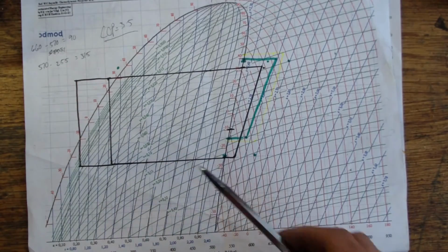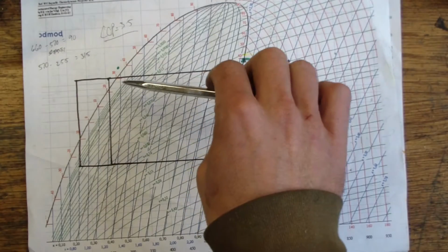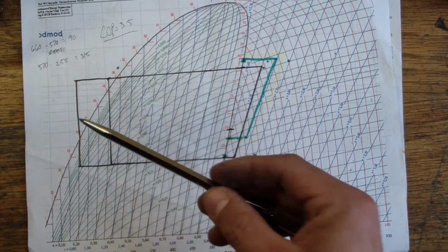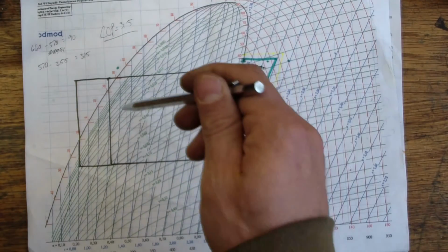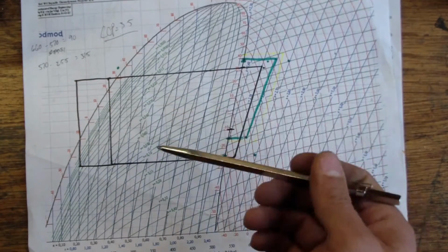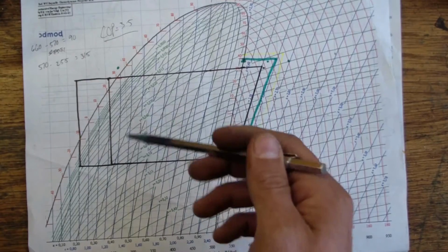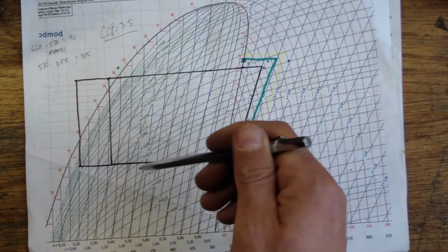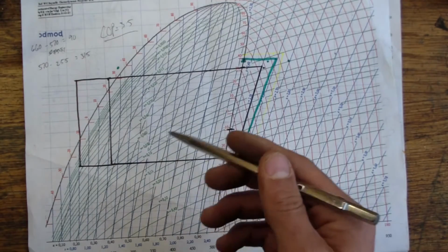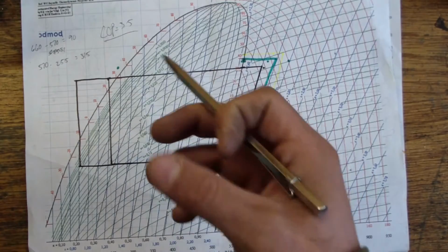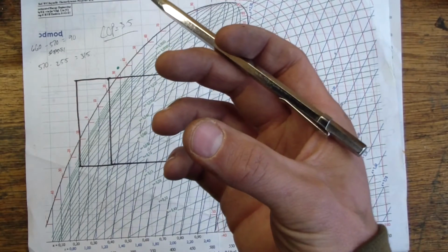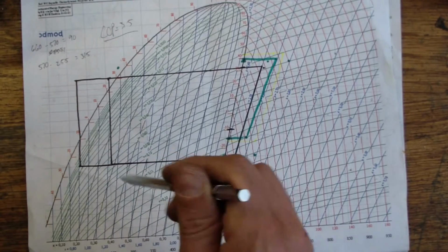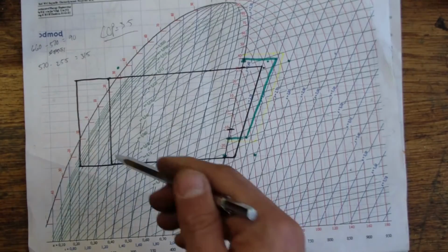we enter an area of the evaporator that's at a much lower pressure. And most of that pressure component that turns into velocity ends up finally resulting in flash gas, because all that high-speed liquid refrigerant coming out of the throttling device immediately starts to get very turbulent and all mixed up, and it essentially amounts to kinetic energy, which is similar to a temperature rise. And if we have a temperature rise, we're immediately above the saturation line already. We're going to get some flash, and some of that refrigerant is going to boil off to absorb essentially the heat energy from that, or the pressure component of the heat content. Not too important here, but we're also going to have some flash because the refrigerant's still at a higher temperature. So upon exiting the throttling device, it self-refrigerates first.